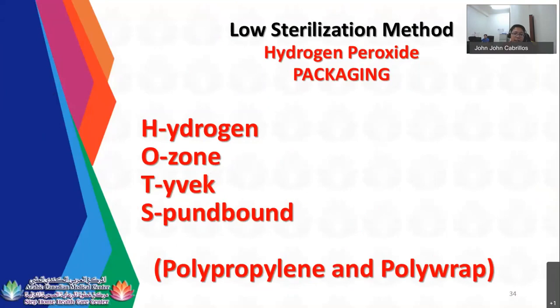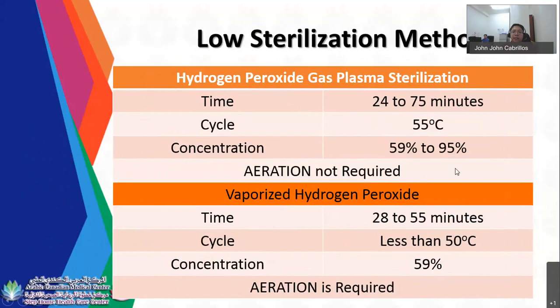So for your hydrogen peroxide gas plasma sterilization, which is the first machine I showed you, or the first video, it has a time of 24 to 75 minutes total cycle. For your temperature cycle, it's 55 degrees Celsius and the concentration of 59 to 95%.